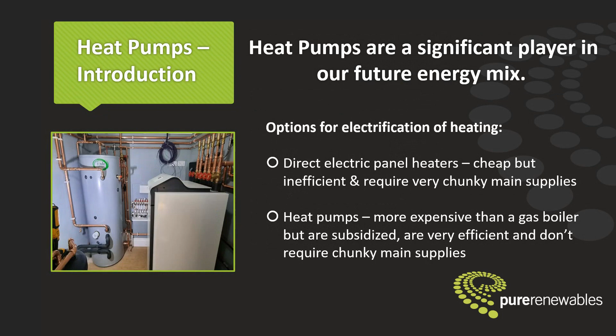If, as in the early days, there was a bit of a finger in the wind approach to sizing heat pumps to a property, even new build properties, then that's often where issues and problems arose because heat pumps were sometimes undersized, which would mean that they would cost a lot to run and wouldn't be effective. But a well-designed system should be very efficient to run and very effective.